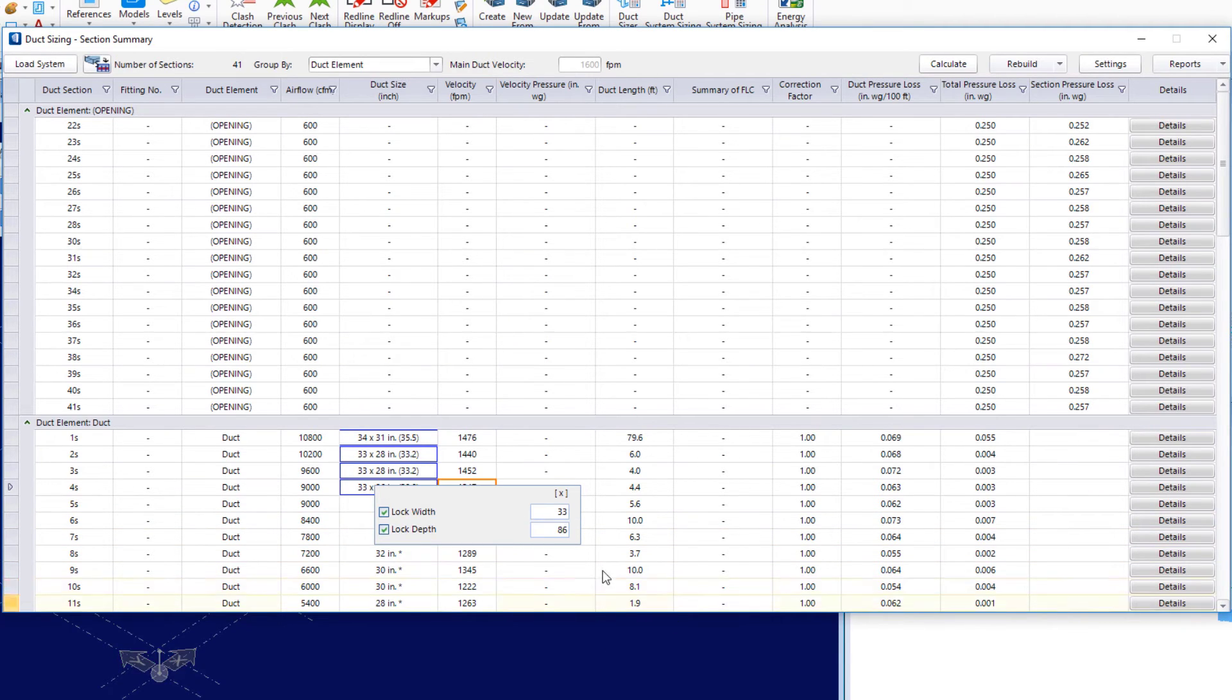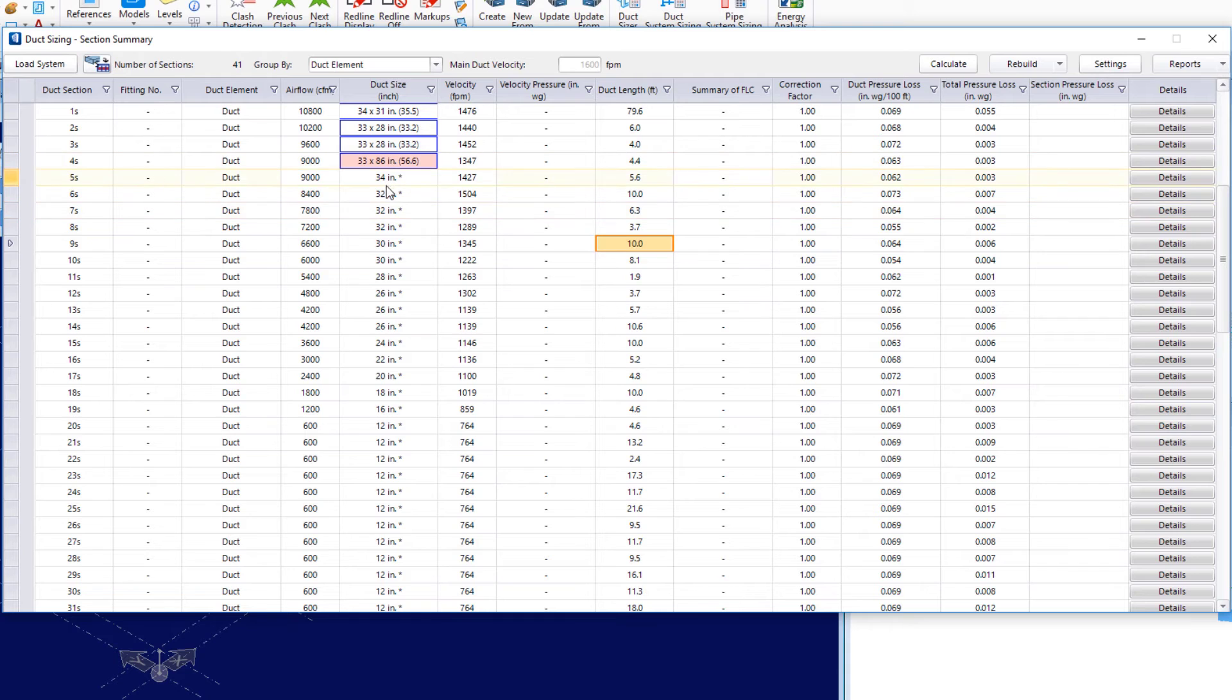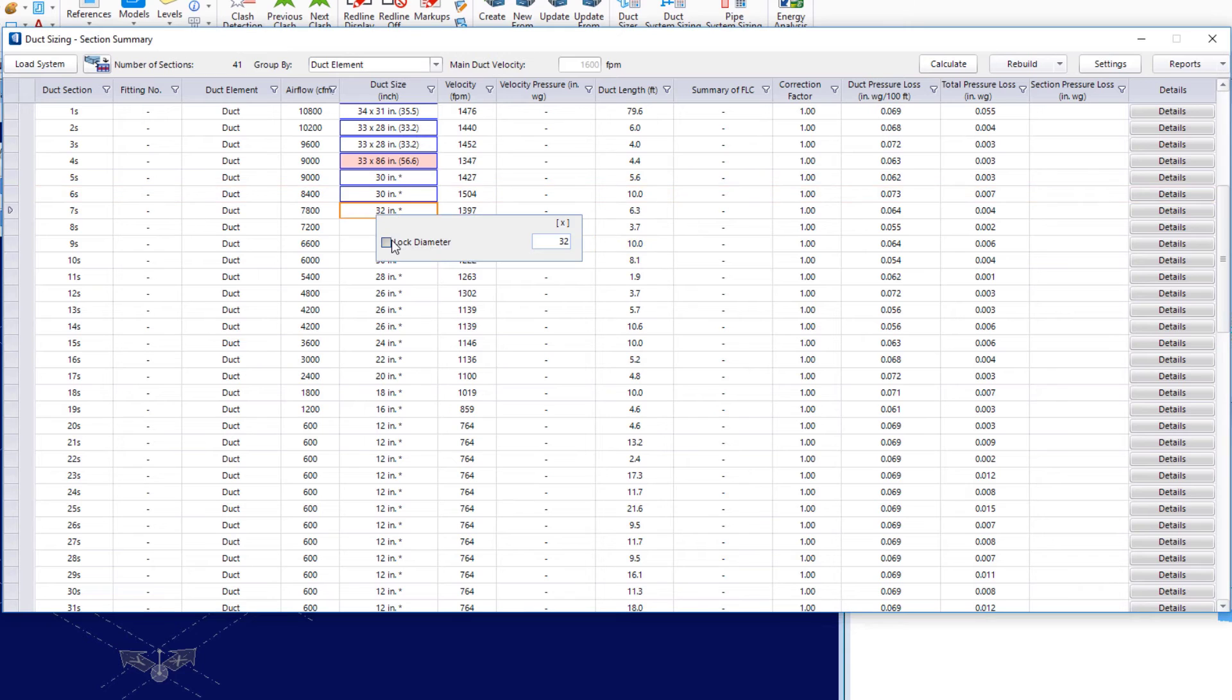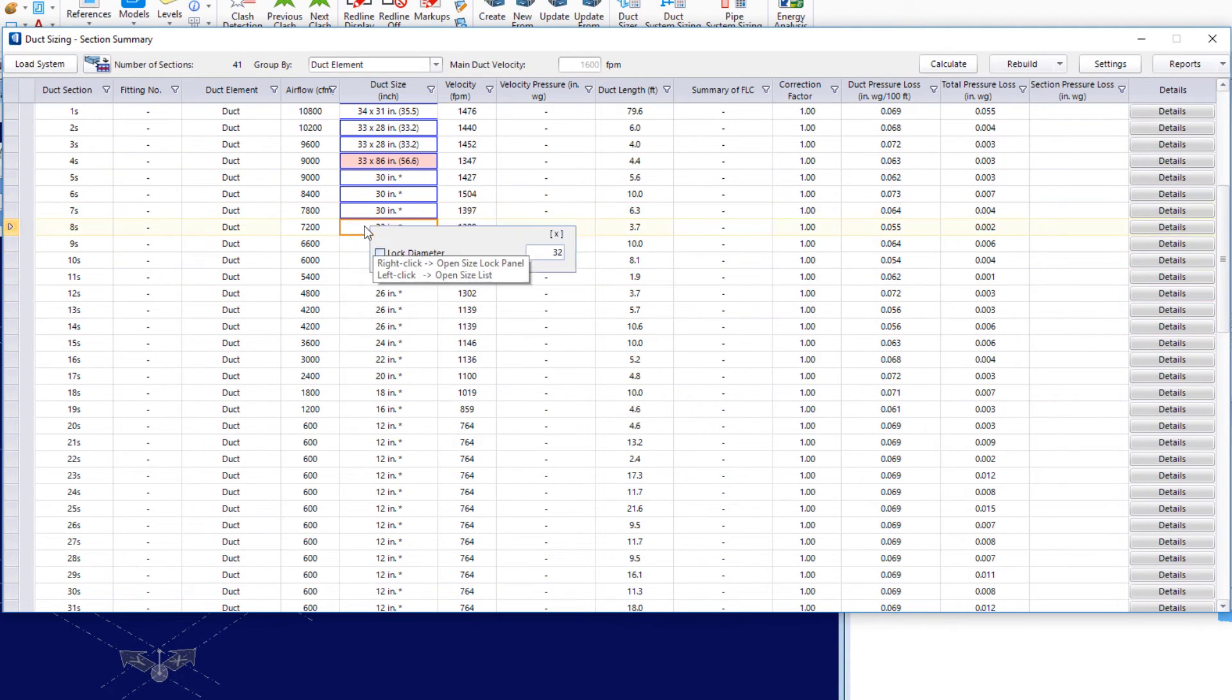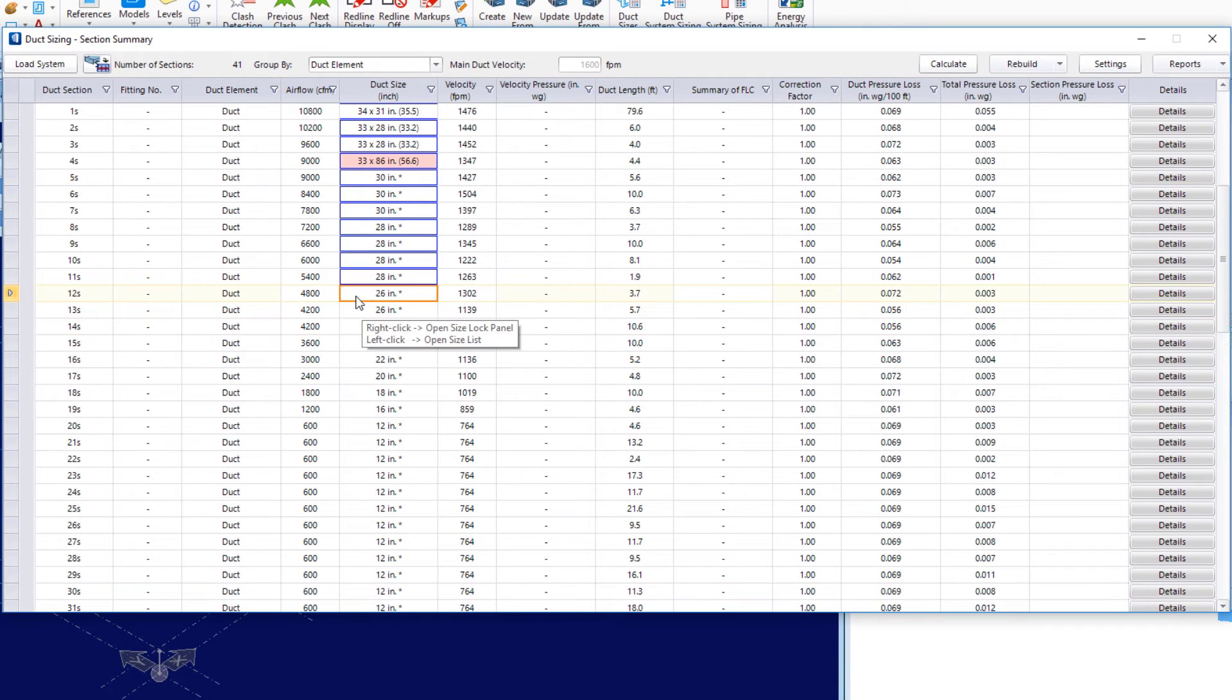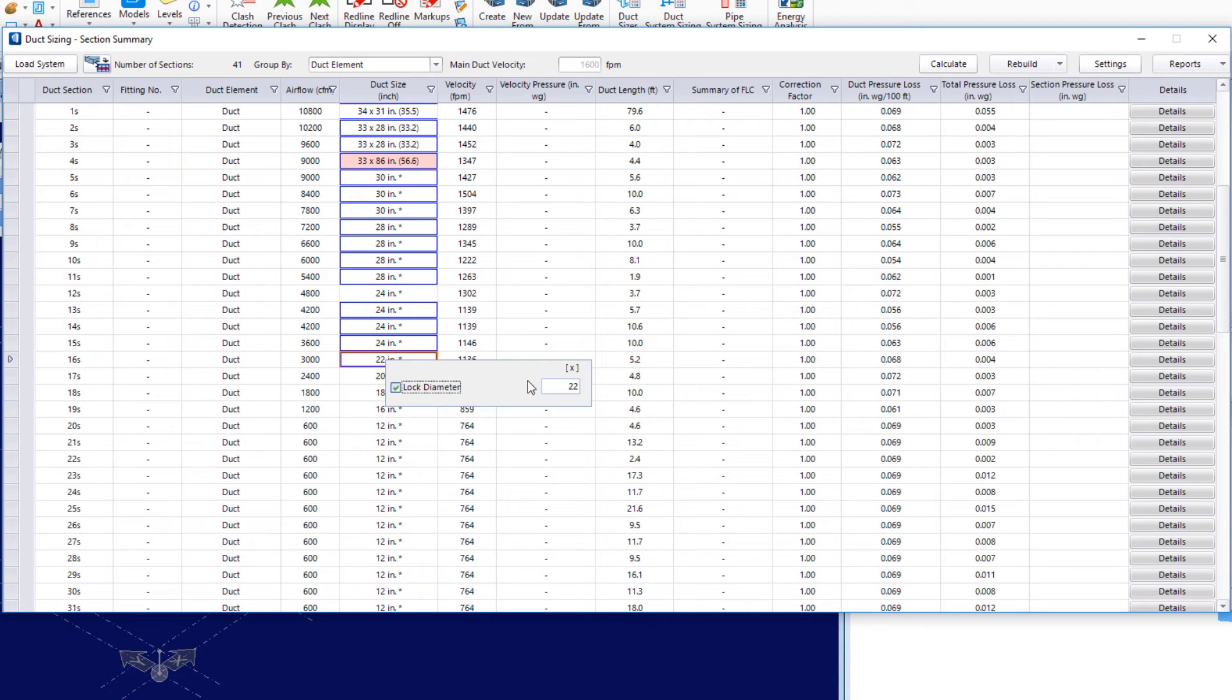And then I'll come down to where I have round duct work. You can see here. So, for elements 5, 6, and 7, I'll make that 30. For 8, 9, 10, and 11, I'll make it 28. For 12, 13, 14, and 15, I'll make it 24. And finally, for 16 and 17, I will make it 22. We're going to calculate.